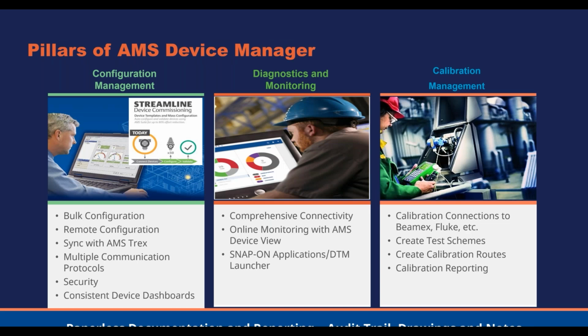With that, I'll jump into what AMS Device Manager is. It's a software that sits on three or four pillars, depending who you ask at Emerson - I like to call it four pillars. The first, and probably most common, is configuration management. When we invented HART in '85 and donated it to the industry, one of the best things about HART devices was that you could configure them - instead of having only one PV value, you can have more, and so on.